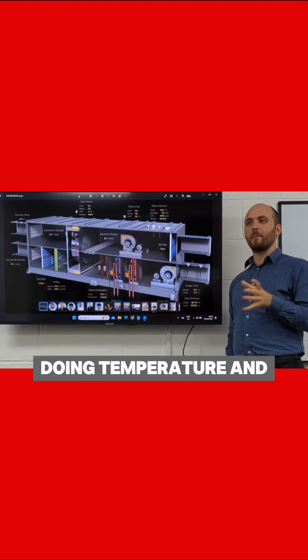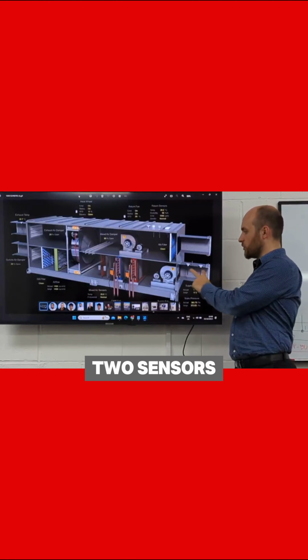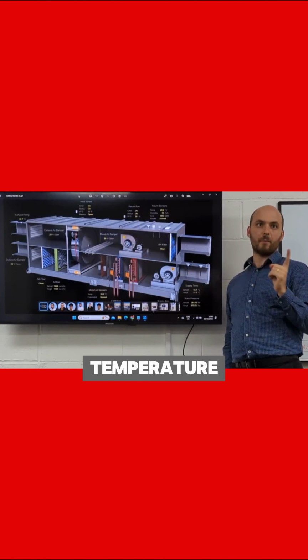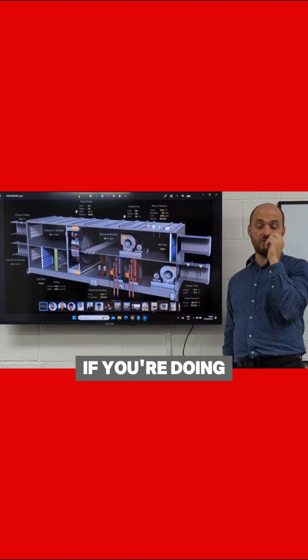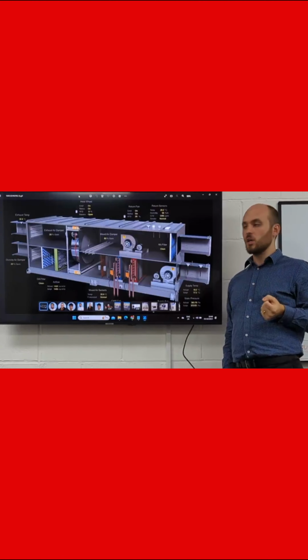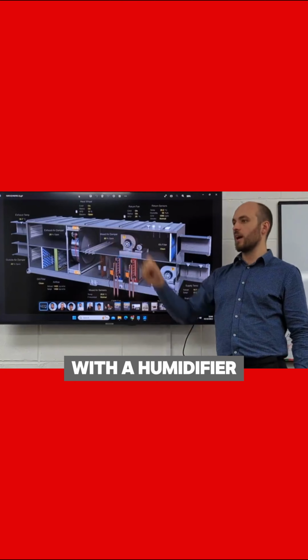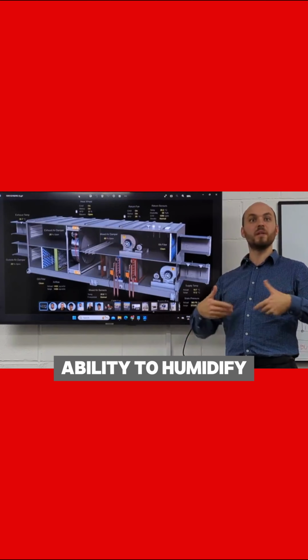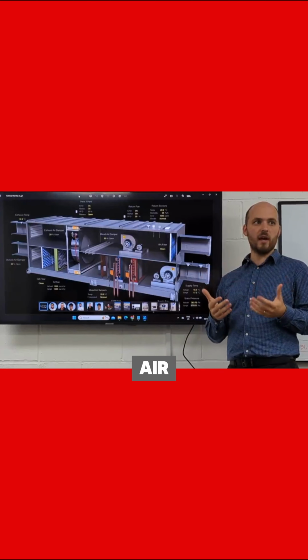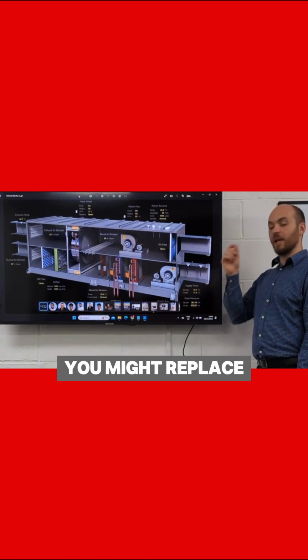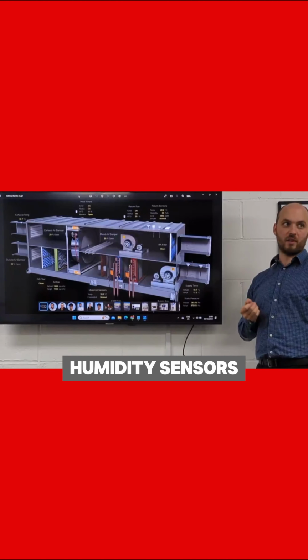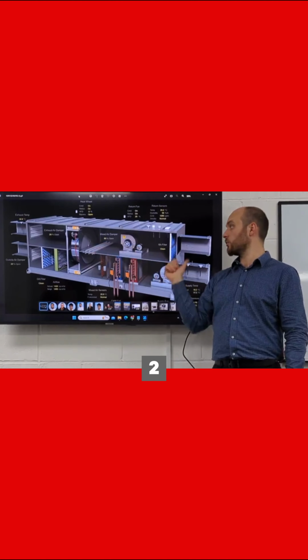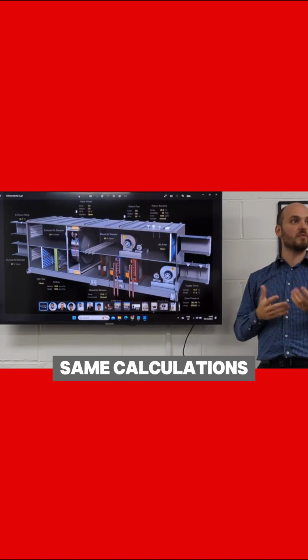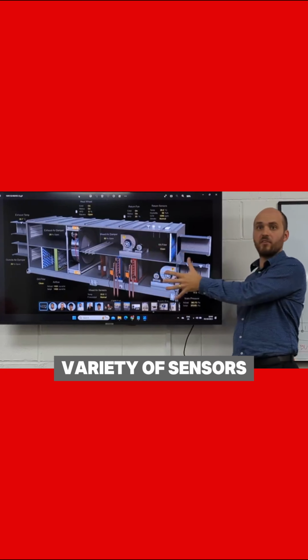If we were doing temperature and humidity though, we wouldn't have 2 sensors, we would have one, which has temperature and humidity built in. If you're doing control to humidity, you could have an air handling unit with a humidifier in there that has the ability to humidify the air, so to add moisture to the air. You might replace those sensors with temperature and humidity sensors. And then again, you'd have 3, 1, 2, 3, temperature and humidity doing the same calculations. But yeah, you could have a variety of sensors here.